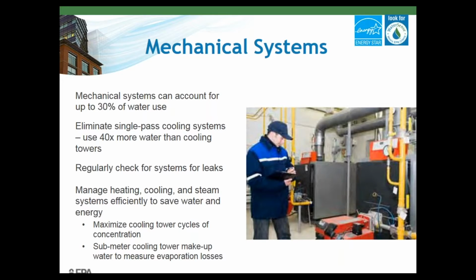Because of the water and energy used, this can be a great place to look for significant savings and a dip in both the utility bill and the water bill at the same time. First thing to do is really eliminate the single pass cooling systems whenever possible. These systems only use water once before it is discharged to the sewer, and they can be really inefficient. Single pass cooling systems actually can use 40 times more water than a cooling tower or another heat rejection source cooling the same heat load.